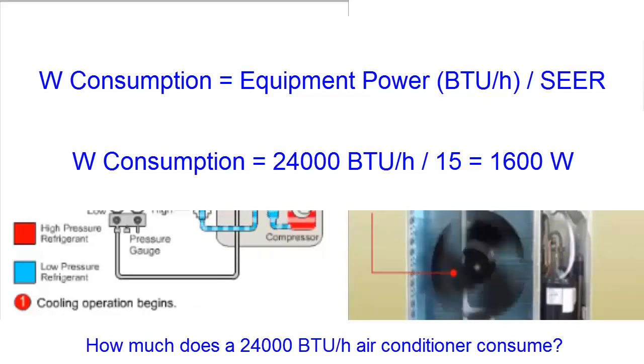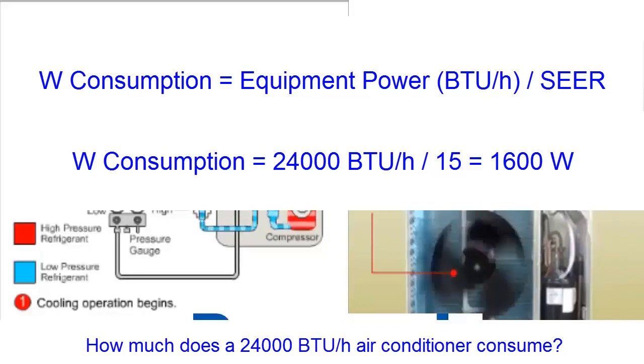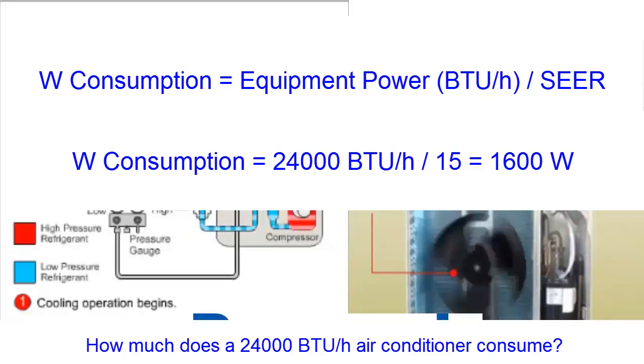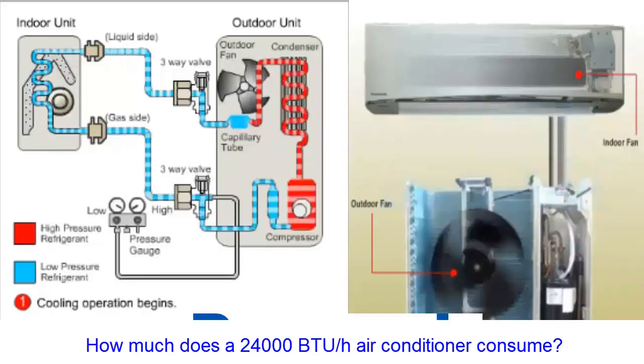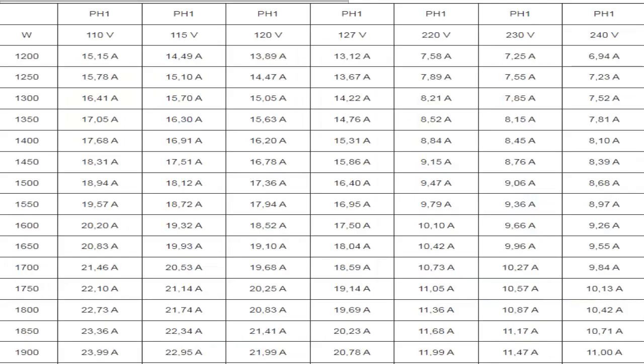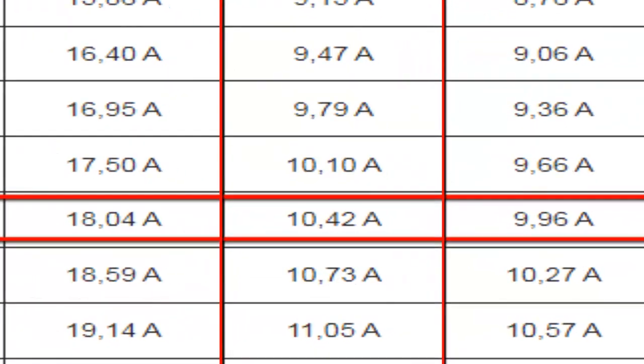For example, for a 24,000 BTUs per hour air conditioner with a SEER of 15, an average consumption of 1,600 watts is expected. With the electrical power consumed by the equipment, you can look up the electrical current value in the amperage table based on the voltage and type of power supply, whether it is single phase or three phase.